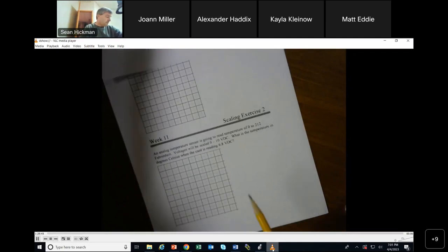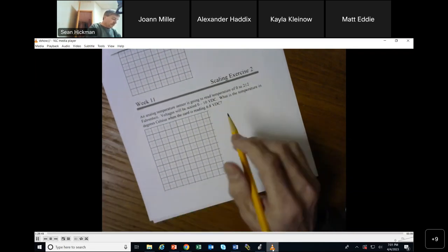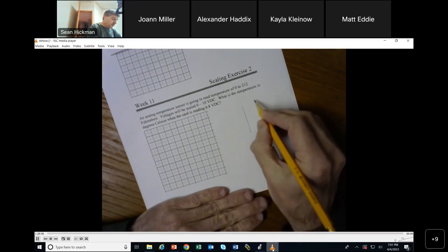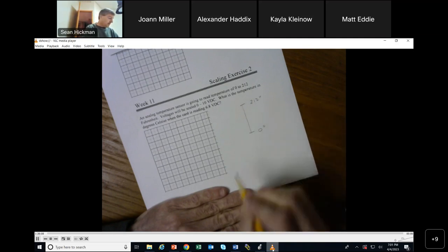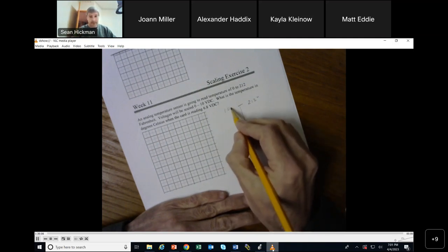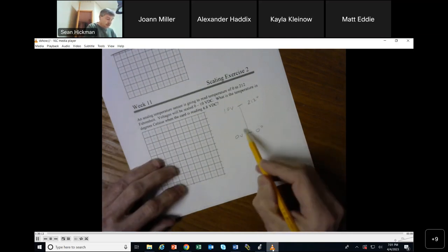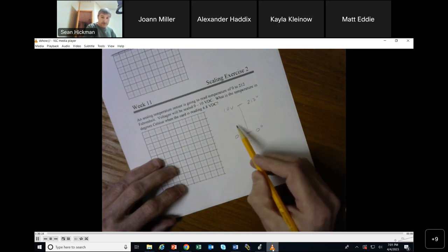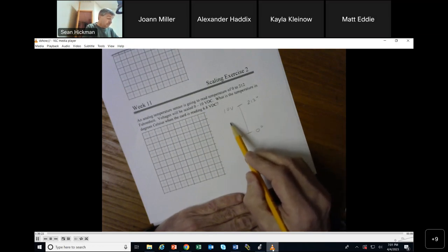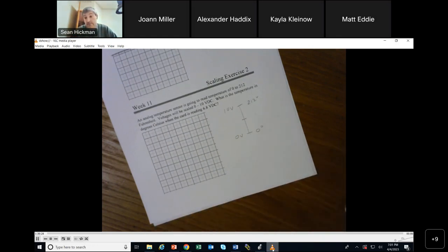All right, so an analog temperature sensor is going to read from 0 to 212 degrees. I'll make this like a thermometer, 0 degrees to 212 degrees. And the voltage will be scaled from 0 volts to 10 volts. This just makes increments, and whatever the ratio of these increments is, it's ratioed to this one. So if I get 5 volts right here, what's the temperature here, everybody?